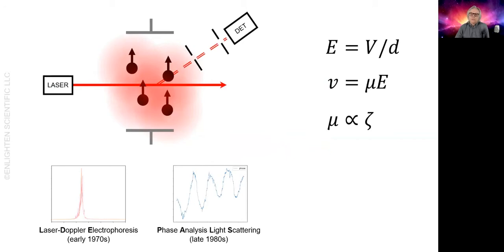Why would you want to do this? The laser Doppler method has a limitation as far as how much electrolyte you can have present in your sample. As you increase the electrolyte concentration, you start to see adverse effects like heating or bubble formation at the surfaces of the electrodes and other unwanted behavior that makes the measurement impossible using the laser Doppler method. Phase analysis gets around some of these limitations, but sacrifices the ability to show you the distribution.